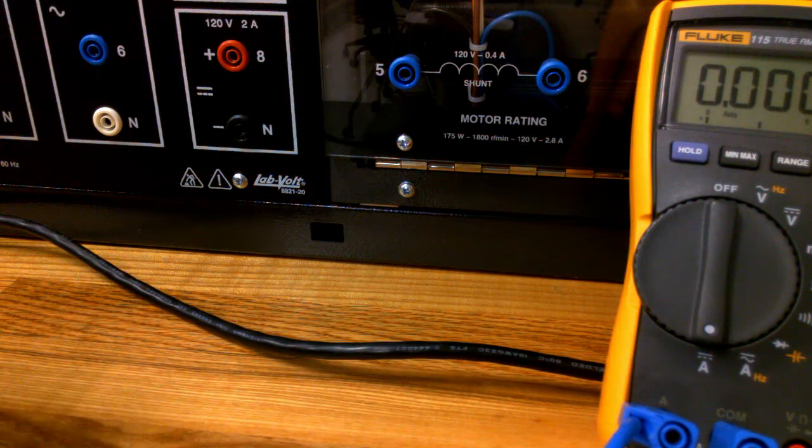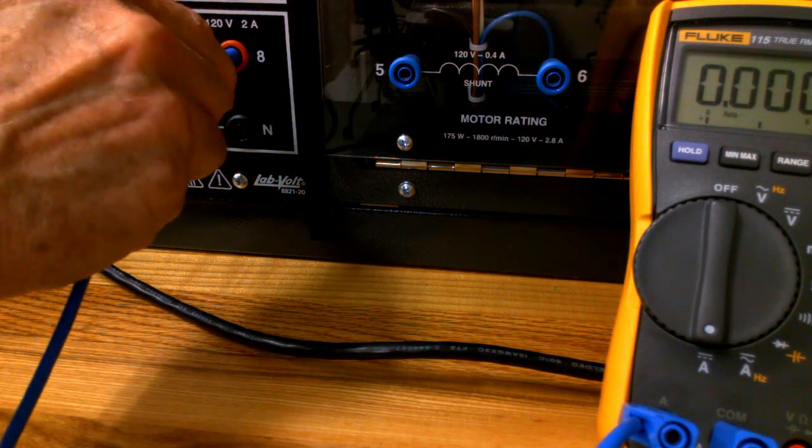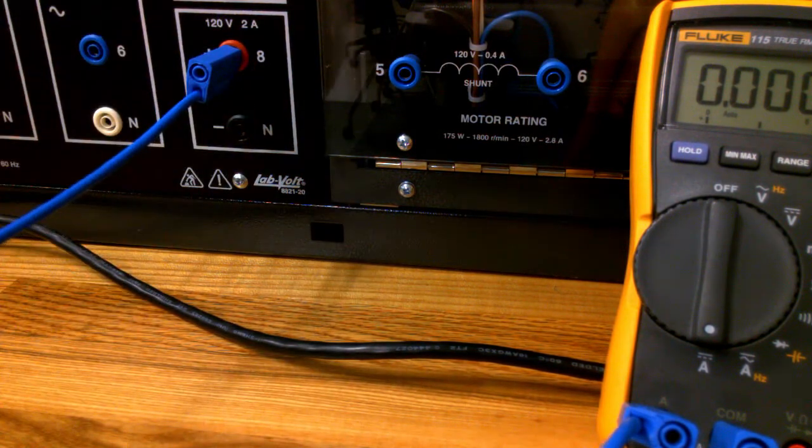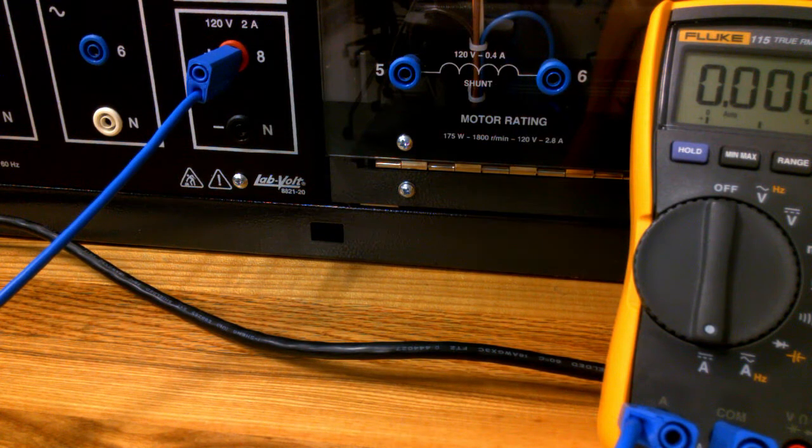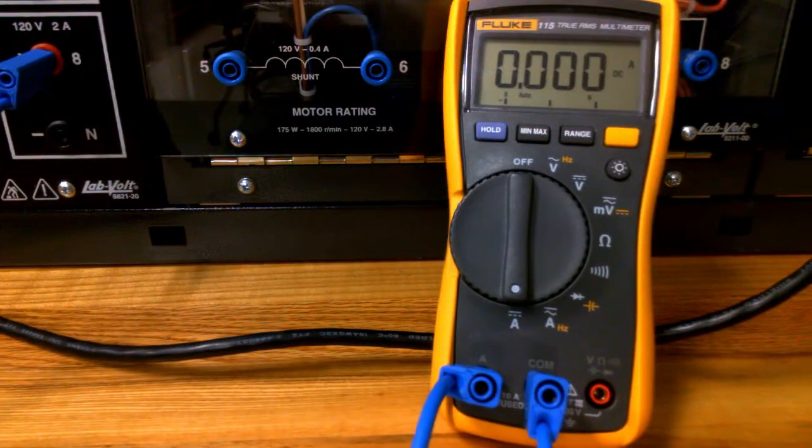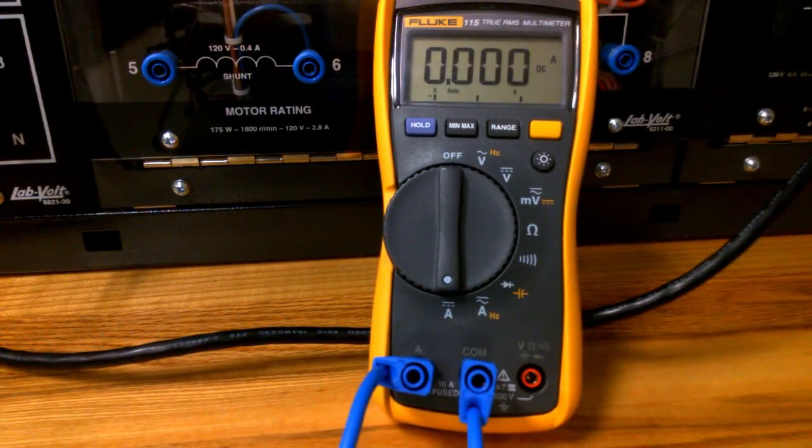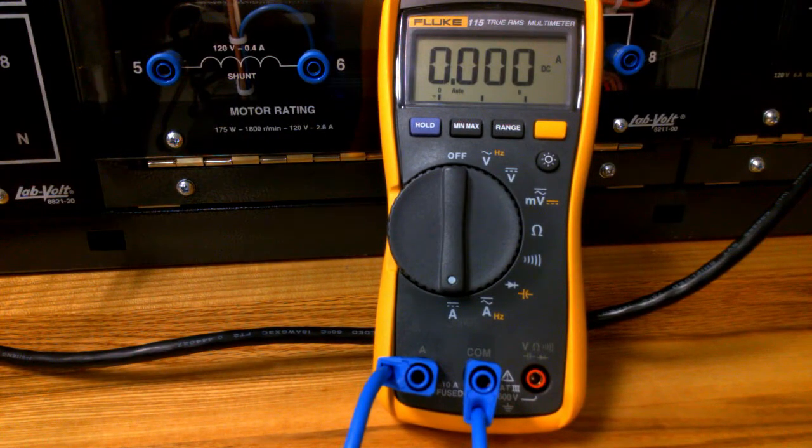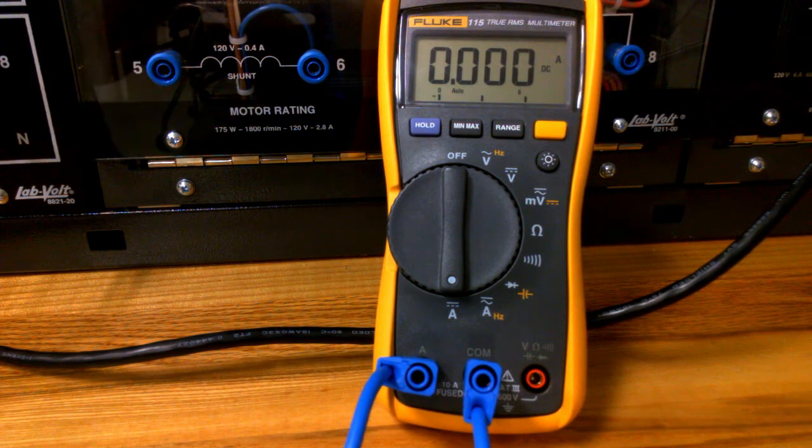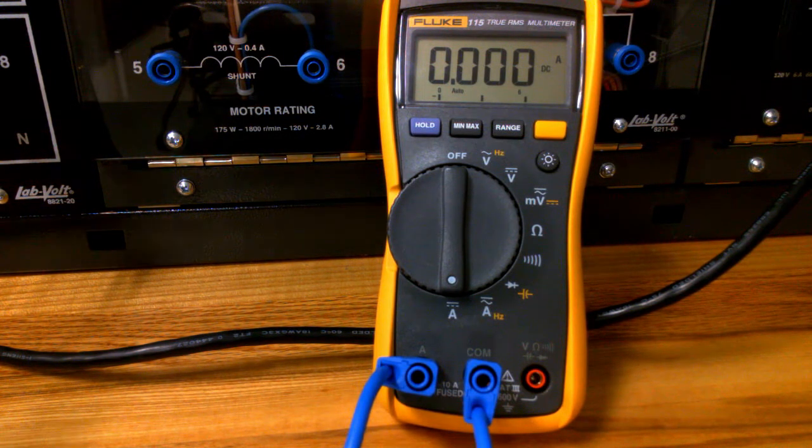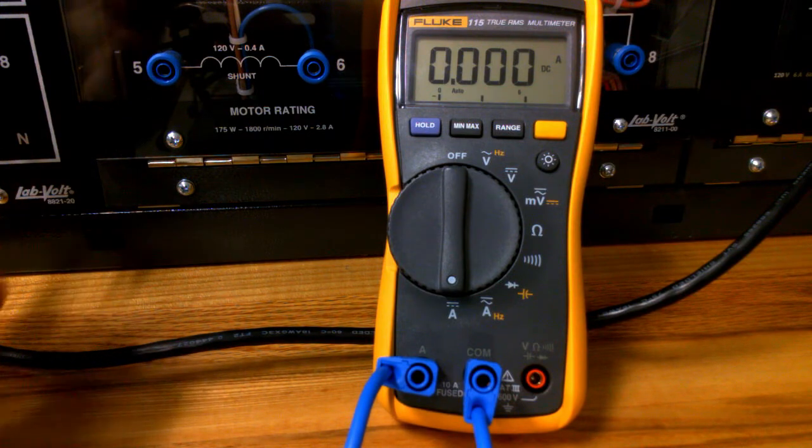My intention was to be measuring current through a winding. You can see right here I'm plugging it in, this is a meter lead by the way, into the 120 volts fixed with great intentions of making other measurements. Remember that when the meter is in the ampere settings, it offers almost no resistance to a hot circuit.